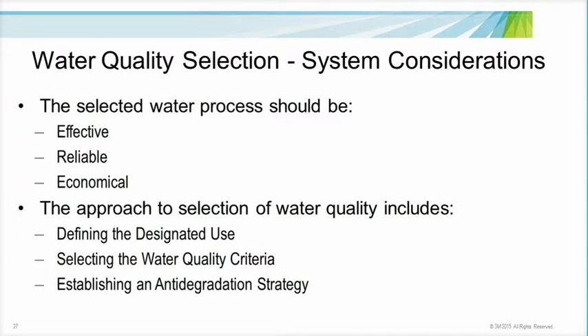Proper selection of water quality in conjunction with system considerations are key as in any process design. The selected water process should be effective for the given process or product need, reliable or sustainable, economical. For example, RO will definitely provide high-quality water, but the process may only require ultrafiltration. A common approach to proper selection of water quality includes defining the designated use, identifying water quality criteria, and finally establishing anti-degradation strategies. Defining the designated use is the first step in identifying what water will be used and what impurities should be removed for the process or product.